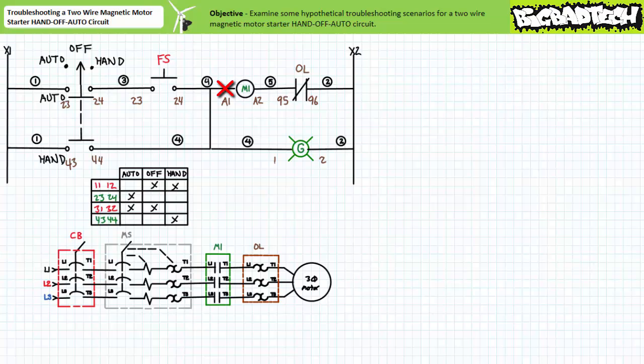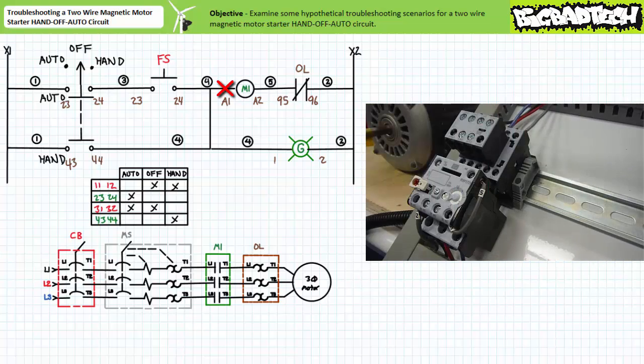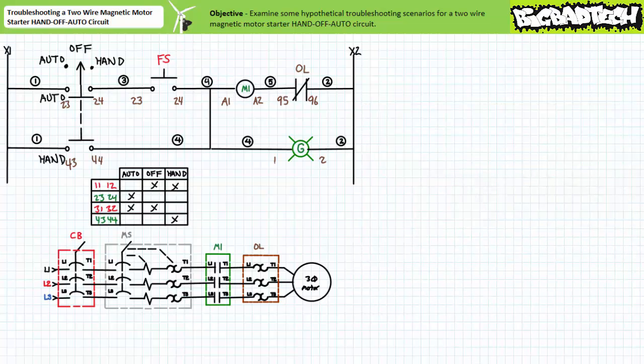Warning, do not try this at home. For this simple circuit, a technician can quite simply manually close the contactor using the manual override on the front and keep forcing it closed until the system can be stopped and serviced. For obvious reasons, this is not the preferred method when dealing with a larger, more complicated system necessitating coordination and relying upon safety critical interlocks.